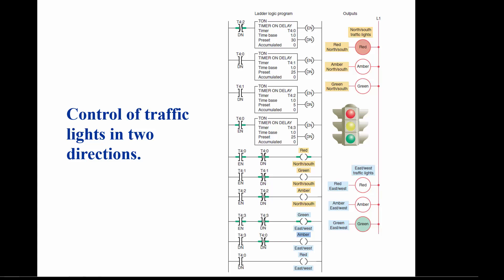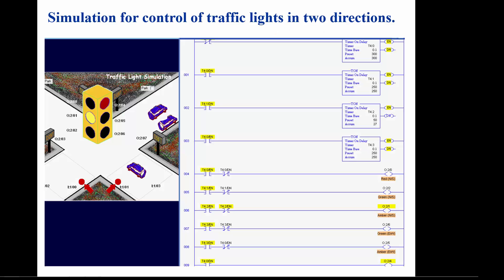The east-west amber is on when T4:3/DN is a 1 and T4:0/DN is a 0. This would be the time between T4:3 finishing and T4:0 finishing, or 5 seconds. The east-west red is turned on when T4:0 is a 1, which is basically when the north-south green light is on. The program will cycle continuously but we will pause the simulation to make it easier for you to examine the status of the timers and lights.